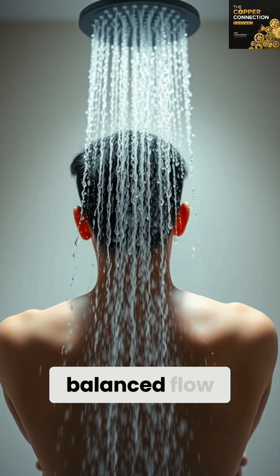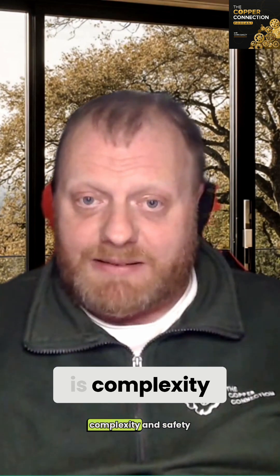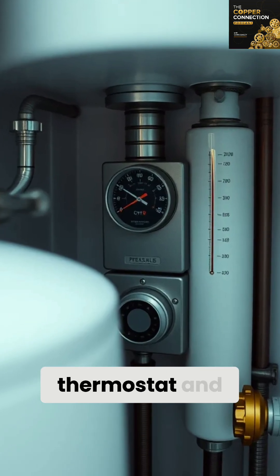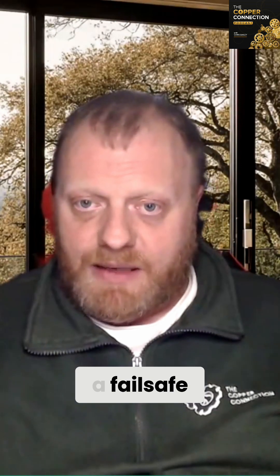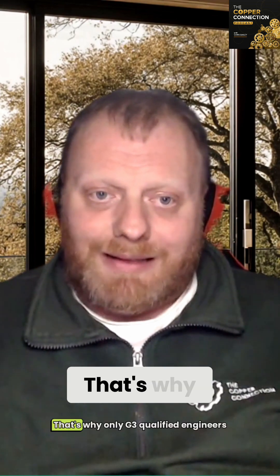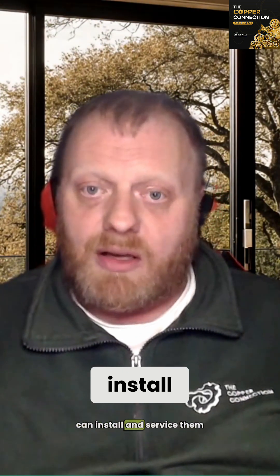High pressure, balanced flow, amazing showers, no cistern taking up loft space — but the trade-off is complexity and safety. You're managing expansion with a vessel, controlling temperatures with a thermostat, and relying on relief valves as a fail-safe. It's a sealed, pressurised system, so everything has to work perfectly. That's why only G3 qualified engineers can install and service them.